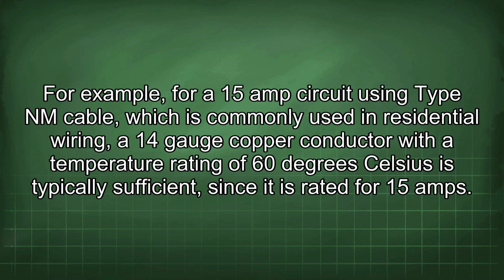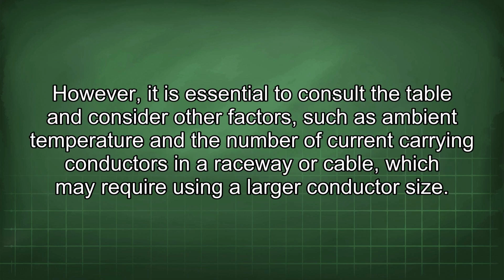For example, for a 15 amp circuit using type NM cable, which is commonly used in residential wiring, a 14 gauge copper conductor with a temperature rating of 60 degrees Celsius is typically sufficient, since it is rated for 15 amps. However, it is essential to consult the table and consider other factors, such as ambient temperature and the number of current carrying conductors in a raceway or cable, which may require using a larger conductor size.